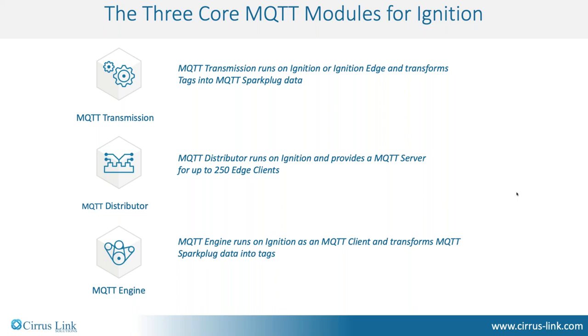The Transmission module runs on Ignition for full systems with many thousands of tags, and also comes as a standard piece of the Ignition Edge MQTT software. It has built-in store-and-forward capabilities for when you lose communications, a server goes down, or the primary host Ignition goes down. It also utilizes report-by-exception capabilities where you can reduce bandwidth over MQTT anywhere between 85 and 95 percent. It has self-discovery features and publishes metadata of tags including scaling, engineering units, high and low ranges, and with Ignition 8 you can add custom properties like asset ID.